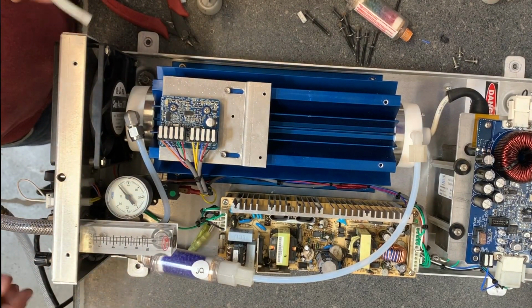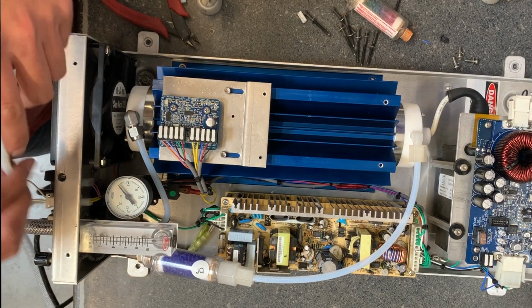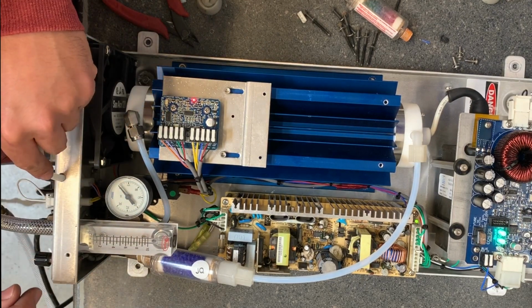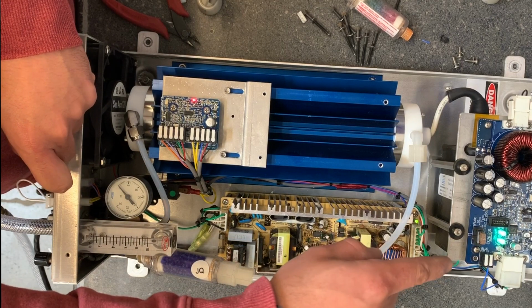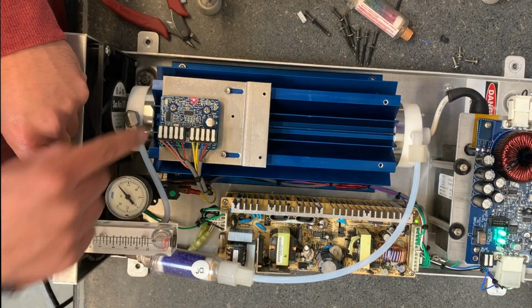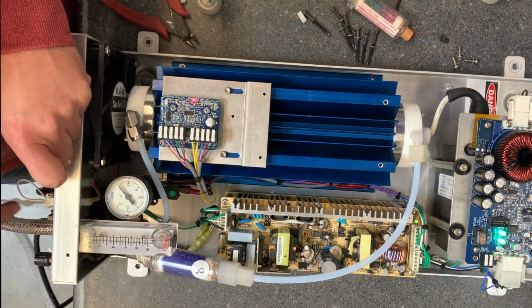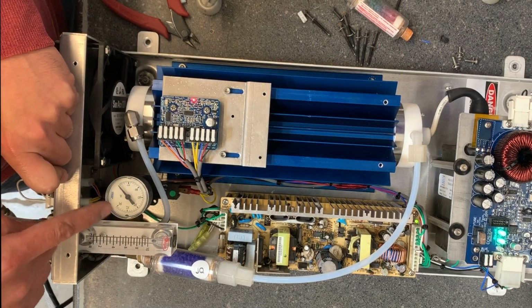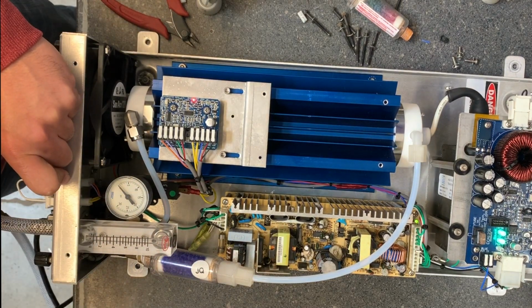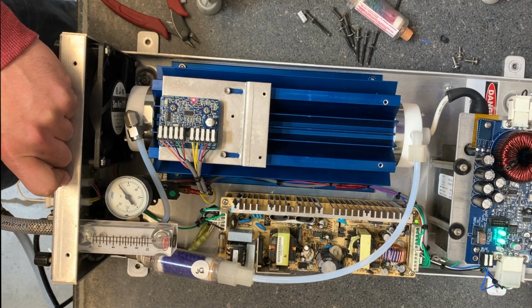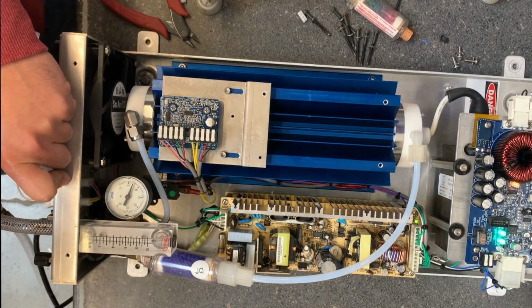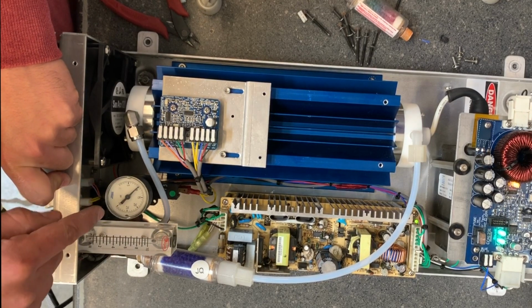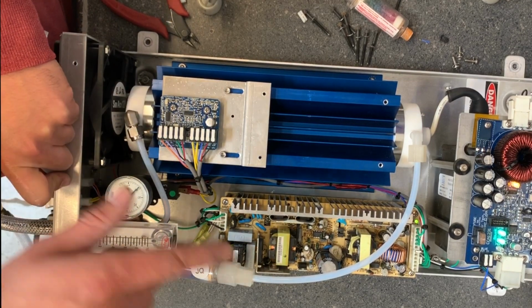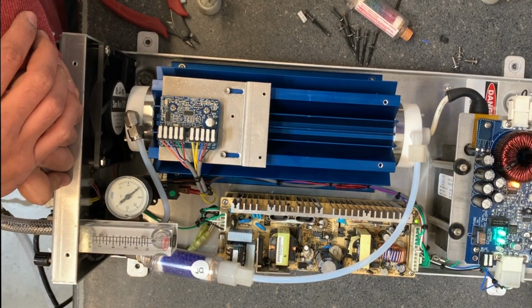So we're going to go ahead and activate the cover switch. Fan kicks on, we get both green lights to kick on. We have our fault light here because we already have dry contact in place. Now we just got to satisfy this pressure switch. So we're going to turn on our oxygen unit or whatever you're using to pressurize your unit. Once we hit 8, it satisfies, red light goes away. We have our drive system kick on.